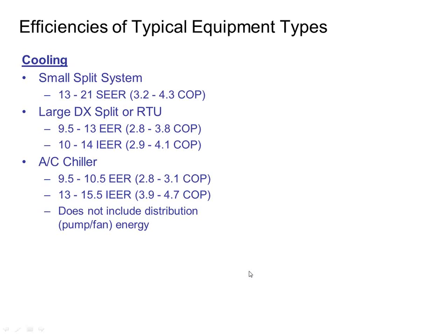I don't know if that's just the way it worked out or that's on purpose. I'm not sure. These rating systems are really good, however, at comparing the same system type, manufacturer A to manufacturer B, or even the same manufacturer, choice A to choice B. Right? So if I want to look at 2 rooftops and compare them, this is a good way to do that. If I want to look at 2 chillers and compare them, this is a good way to do it. If I want to compare an air-cooled chiller to a water-cooled chiller, probably not the best way to do it. If I want to compare a boiler to a VRF, definitely not the best way to do it.